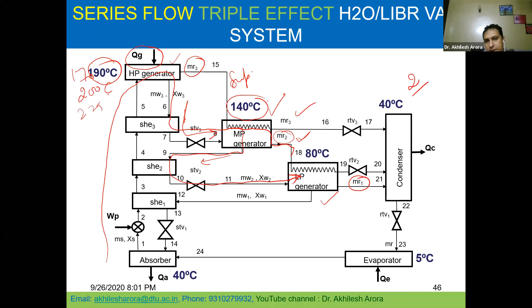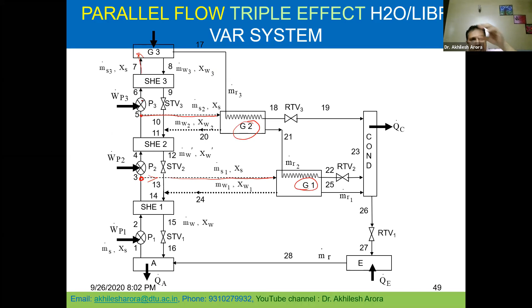In parallel flow, what we have done here is divide this flow. This is the first point where I have divided the flow. It goes to G1, the lowest pressure generator. Then I have divided it here, and it is going to the medium pressure generator. Then the remaining solution goes to the high pressure generator. So it has been divided in parallel. That is why it is known as parallel flow triple effect.